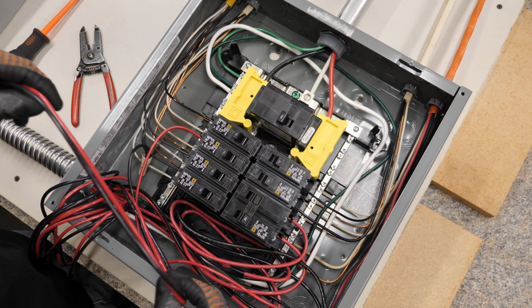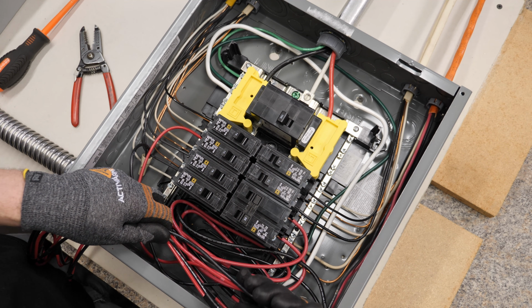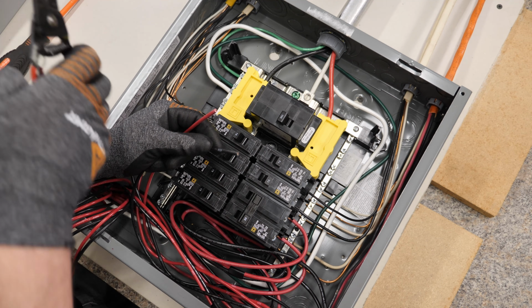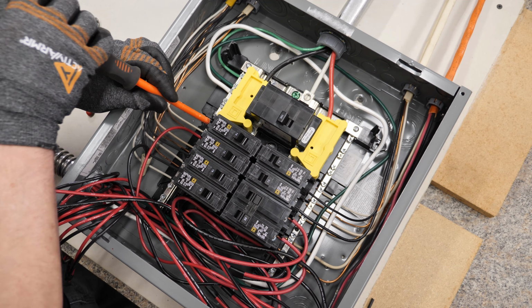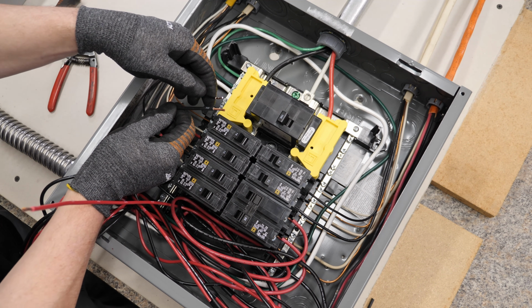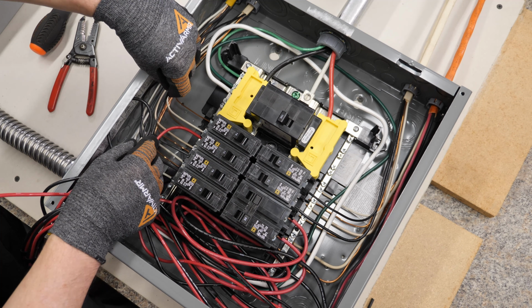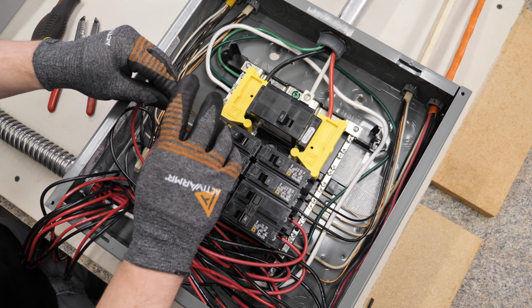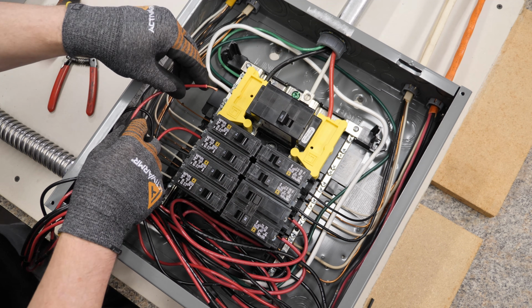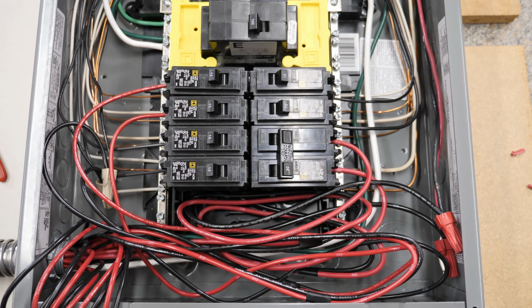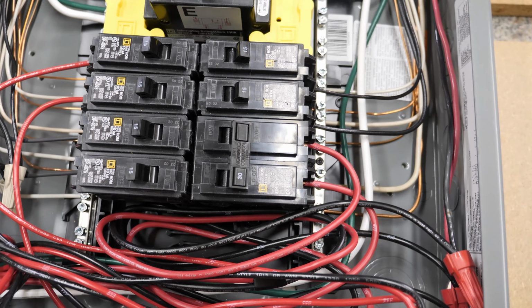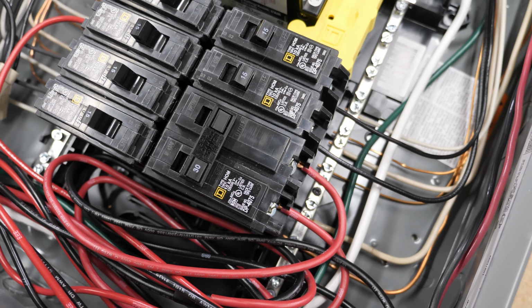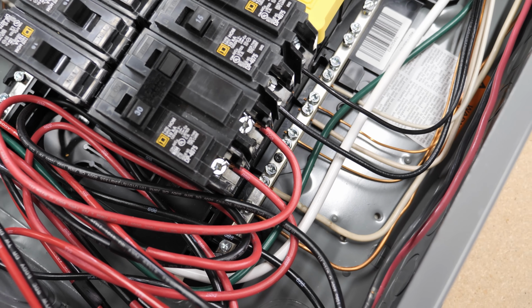We just have one more left to do, which is circuit breaker 1. I'm going to strip back the wires again, remove the wire, pull that out, go black to black, move that wire out of the way, and then insert the red wire into the circuit breaker. Boom, and done. So we have a 240 volt double pole circuit breaker wired up right here.